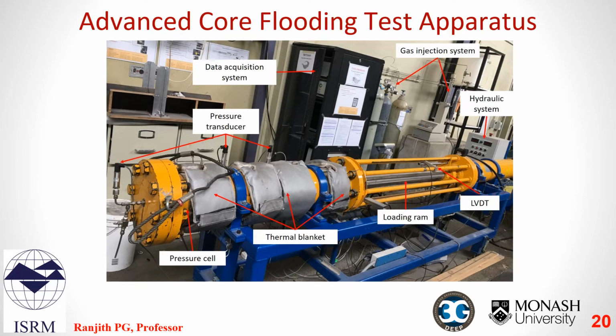Next, let's have a look at the key features of the advanced large core flooding apparatus. This apparatus consists of four main elements: high pressure cell, hydraulic loading system, fluid injection system, high precision measuring and data logging system. The maximum working temperature of the facility is currently at 100 degrees C, and the cell is covered with a thermal blanket to achieve the operating temperature. This temperature can be modified to even higher temperatures of up to 200 degrees C.